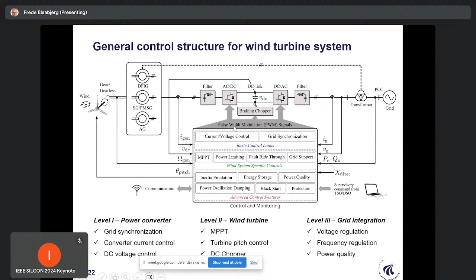So the converters we are applying are gradually changing, but there's no doubt that the absolute main converter topologies are operating below 690 volt. The reason for that is that then we have one kind of security protection system. If it enters into medium voltage, then different features are needed in order to have a safe system. So what is very often used is a two-level voltage source converter with filters, as you can see here. So we can control the generator and we can control to the grid.